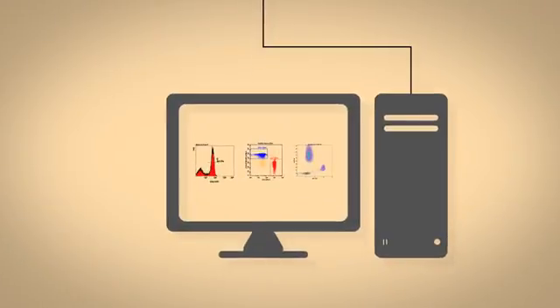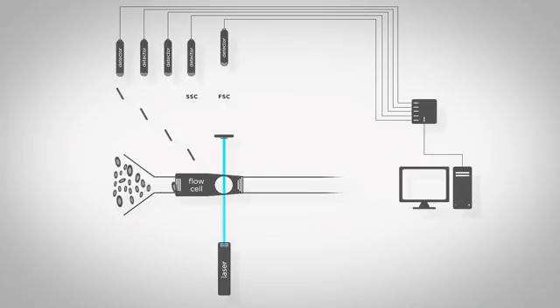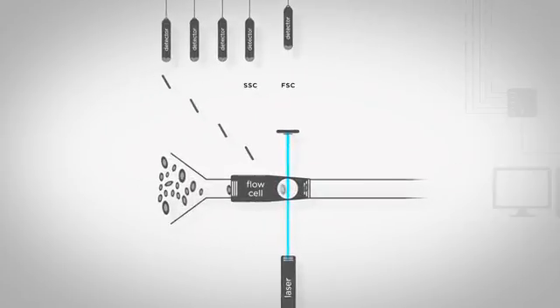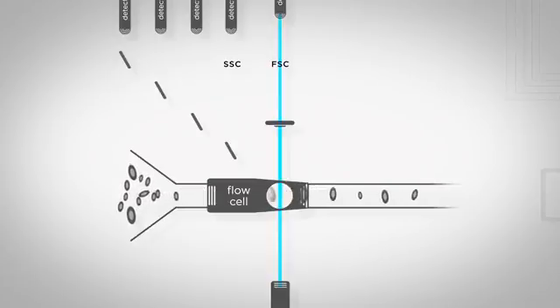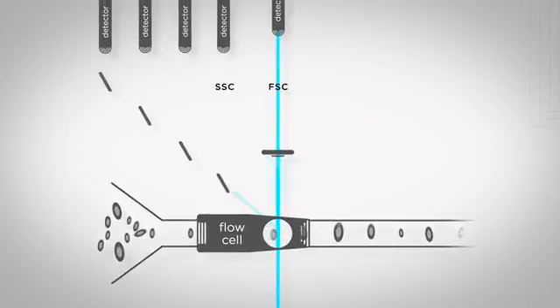So how does the flow cytometer analyze cell characteristics? As the sample moves through the laser beam, the system captures the light scattered by each cell. In most flow cytometers, a detector in front of the laser measures forward scatter, which reflects relative cell size, and detectors at 90 degrees measure side scatter, which reflects the granularity of cells.